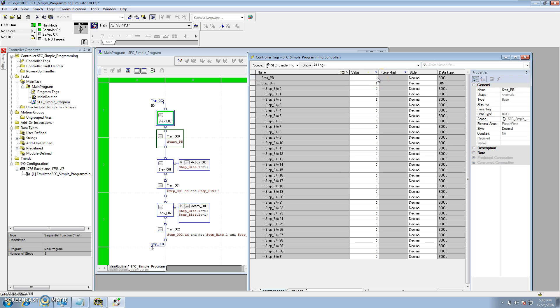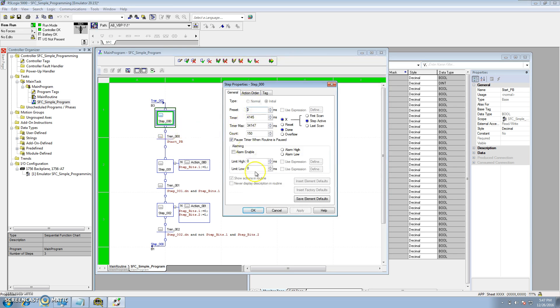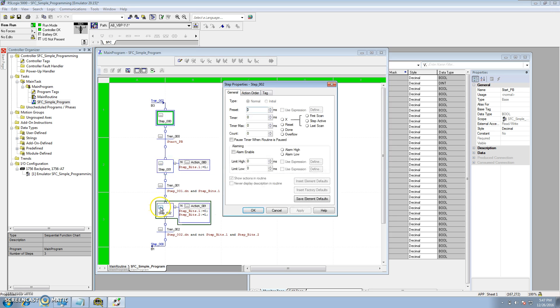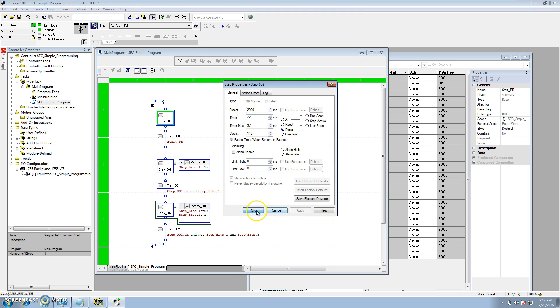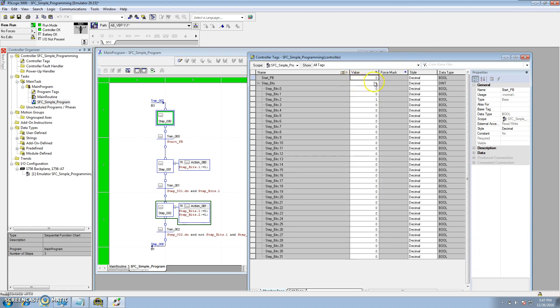If the start is dropped it will stop. What we can do is add timers in the action body — let's say 2000 milliseconds for each step. We'll do the same process: it cuts on, goes 2000 milliseconds, then transitions, and you can see bit 1 cuts on.